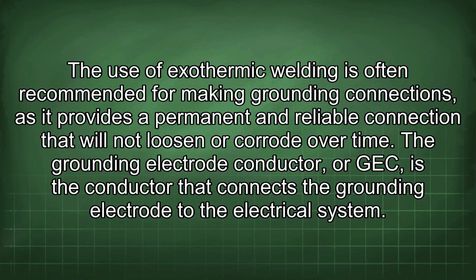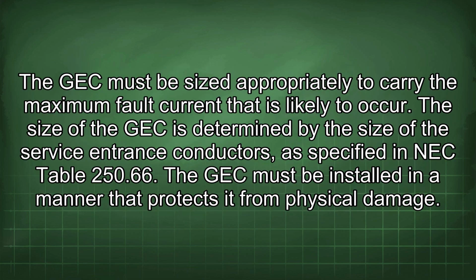The grounding electrode conductor, or GEC, is the conductor that connects the grounding electrode to the electrical system. The GEC must be sized appropriately to carry the maximum fault current that is likely to occur. The size of the GEC is determined by the size of the service entrance conductors, as specified in NEC Table 250.66. The GEC must be installed in a manner that protects it from physical damage.